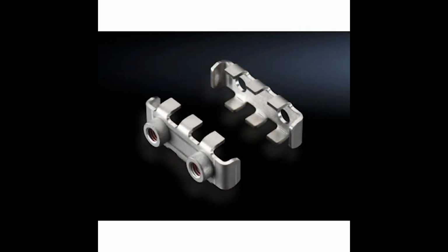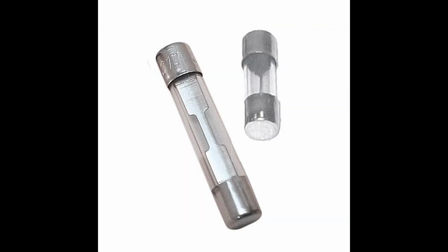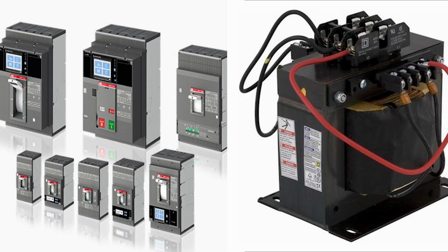Bus bars are another component. These conduct power within the switchgear assembly and distribute it to various circuits. Fuses, as we can understand, melt under excessive current flow and provide overcurrent protection. Current and voltage transformers. These are transformers within the switchgear that measure system parameters and provide data for monitoring and protection systems.